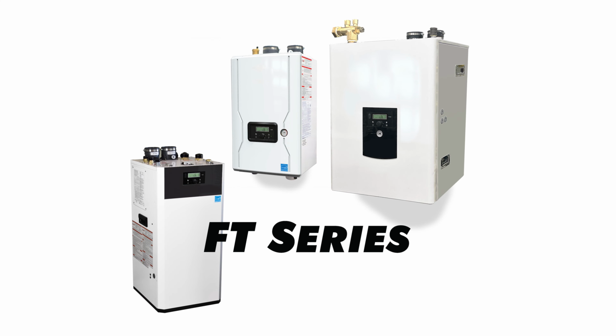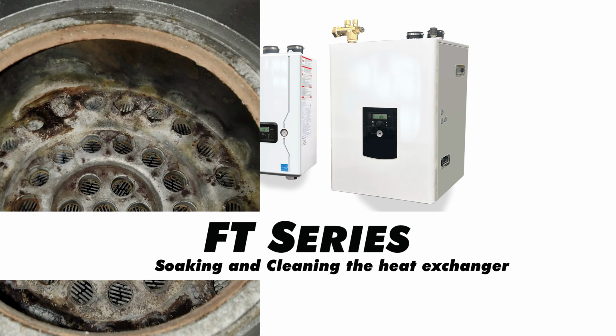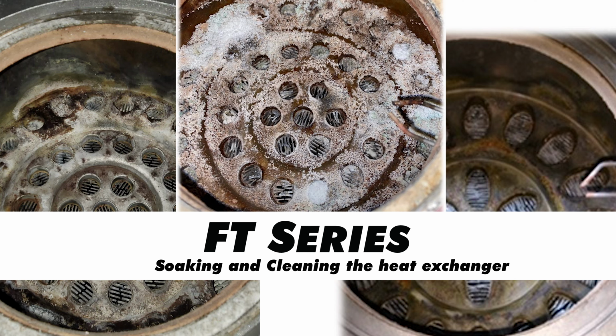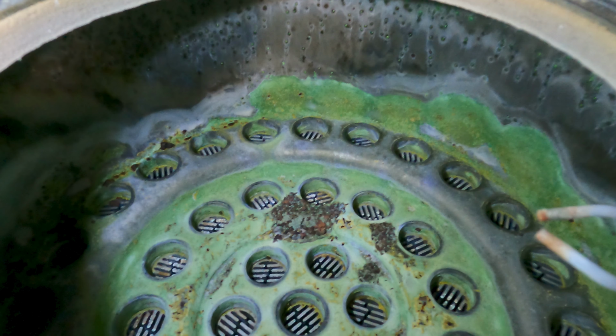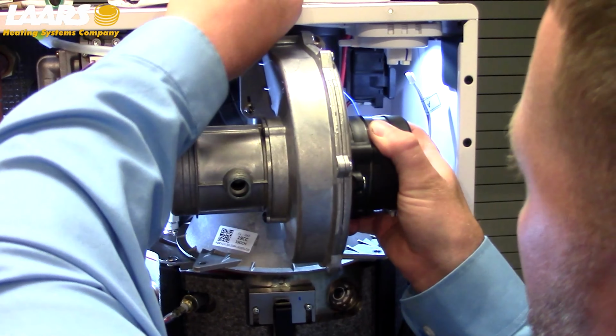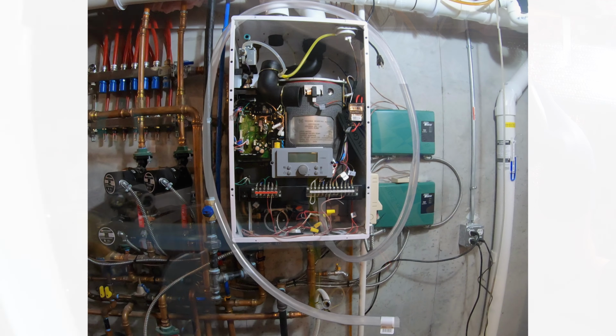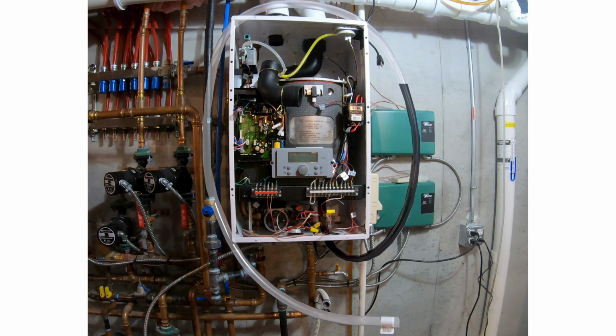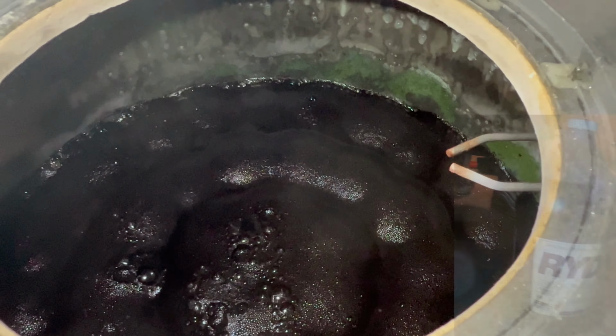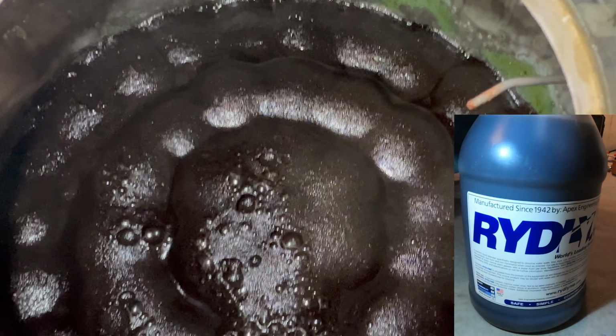The FT series of stainless steel boilers do require an occasional cleaning of the heat exchanger. This is achieved by removing the blower, the intake elbow, the intake manifold, and the burner itself, and then soaking the heat exchanger in about 2 gallons of a biodegradable descaler. RYDLYME is an acceptable brand.